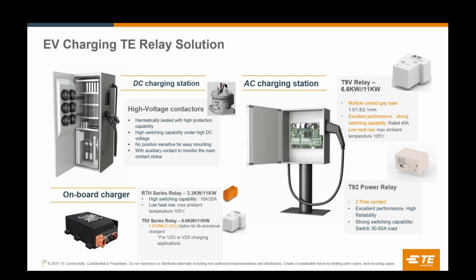As Juan mentioned in an earlier slide, this is broken down into two levels, level 1 and level 2. Level 1 is typically that 120 volt device that might go in the trunk of the car, maybe comes with the car from the manufacturer. It plugs into most places around the country, about 16 amps. It takes a long time to charge the car, but it gives you some option. We've got an RTH relay suitable for the high temperatures that could be seen there. Just two RTH relays should be enough for this level 1 charger. It's about 1.9 kilowatts, not very powerful compared to level 2.